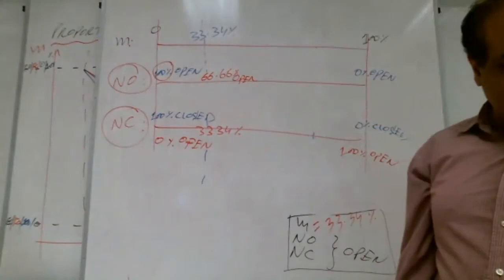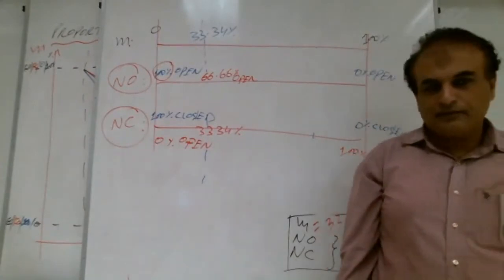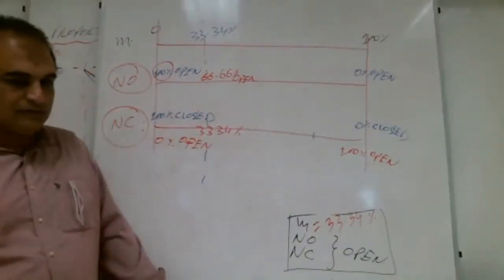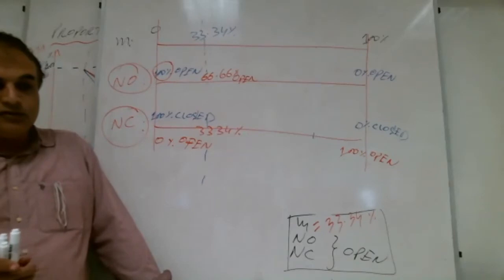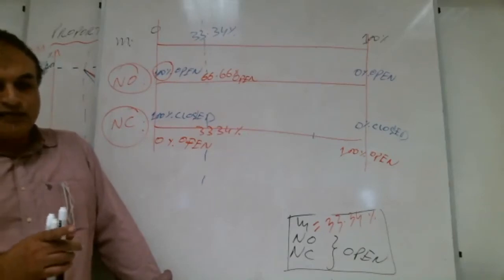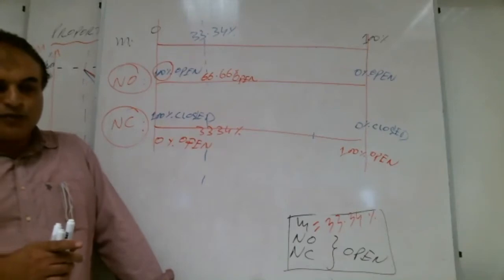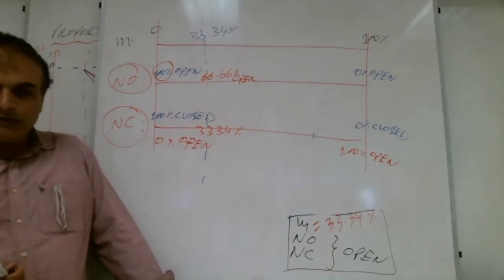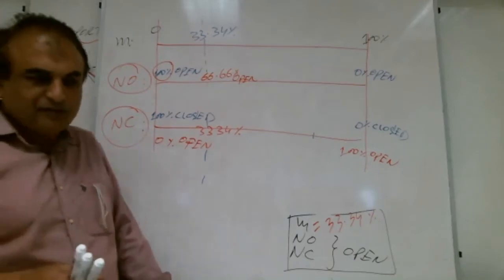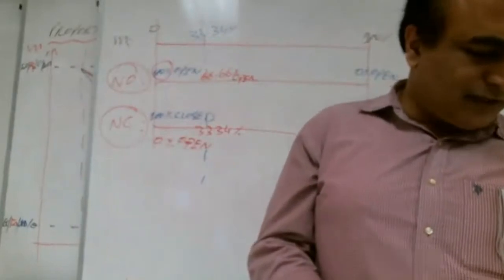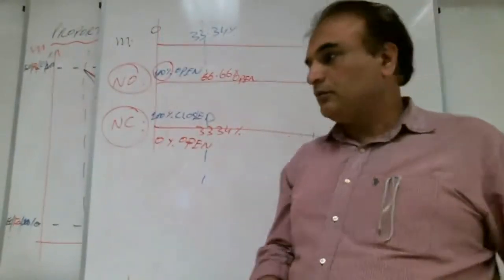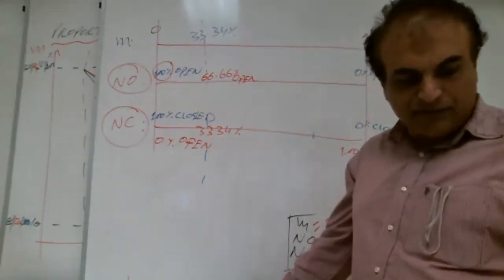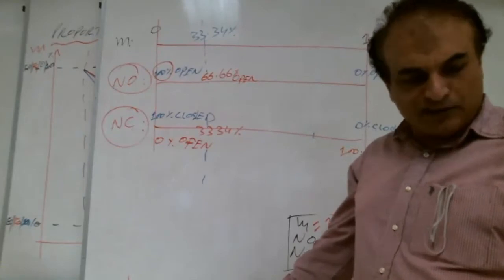Yes, Shabab. I have a question, teacher. Does the proportional band affect the valve opening also, or no? So in the starting, we found the proportional band. The gain was 2. Proportional band was 50%. You remember? In this problem, we start with the gain 2. Okay, the proportional band 50. If we make the proportional band 25, how much will be the gain?